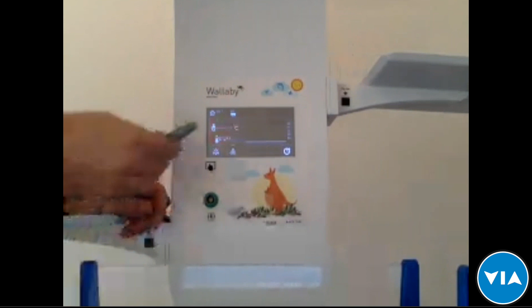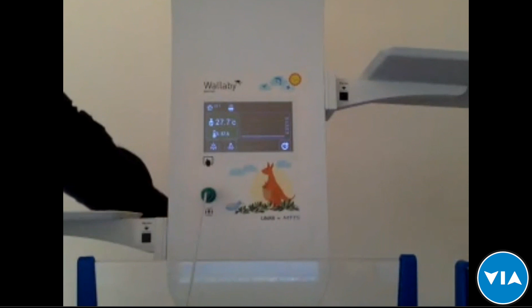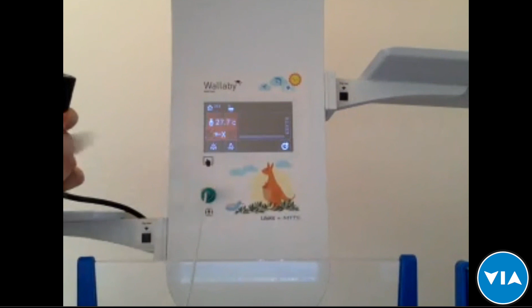If for some reason we have a broken heater element, the alarm rings in a similar way — we get a heater power failure alarm. For example, I'm going to disconnect the machine from the power now. So I've disconnected it, and now we have the alarm — this is the heater power failure alarm.